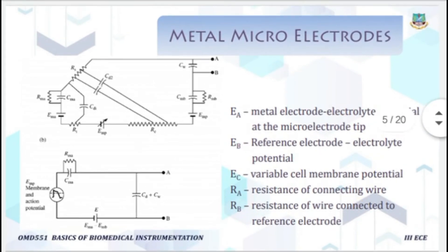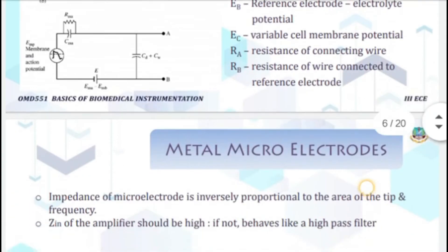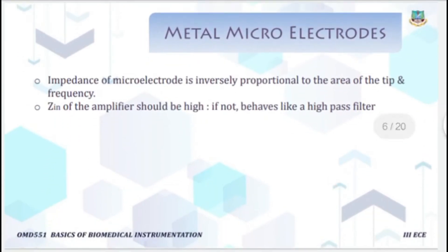To reduce the impedance, some electrolytic processing called chloriding the tip takes place. This is the equivalent circuit of the metal micro electrode. The impedance of the metal micro electrode is inversely proportional to the area of the tip and frequency.